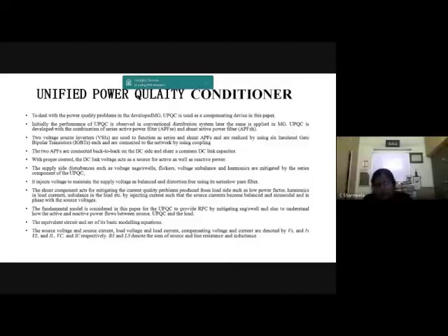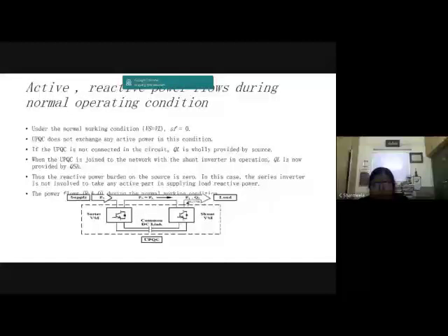So let us go to one more device, which is the unified power quality conditioner. It is a combination of your shunt active power filter and series active power filter, which is going to solve both current and voltage related problems with the help of the UPQC. And this is one such example which we simulated in our laboratory. Here you have the series and shunt compensating devices, and your non-linear loads or UPS loads are taken for understanding. UPS loads are going to inject harmonics of order np plus or minus 1, which means 5th and 7th order harmonics will be predominant. And sometimes there may be voltage related issues also, so we need to deploy a series compensating device which will compensate the voltage related issues. So these are the different PQ conditioners deployed onto the power network to improve power quality problems.